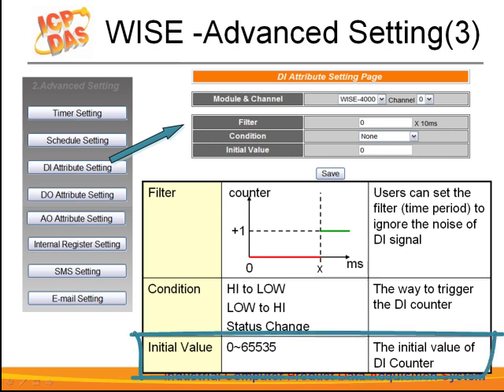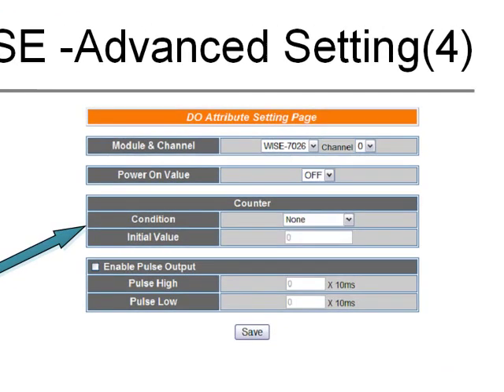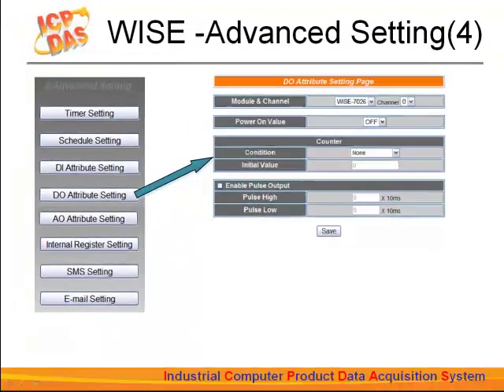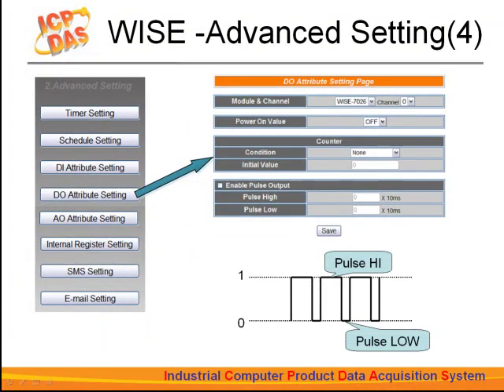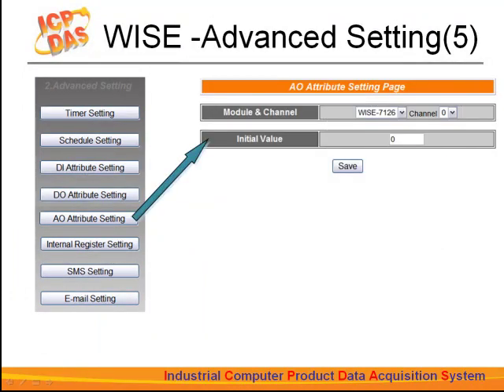You can also set the initial value of the counter in the initial value field. Now let's take a look at the digital output channel settings. You can set the power-on value to be on or off, and you can also set the counter as digital input. DO supports pulse output; you can set up pulse high and pulse low for the periodic pulse cycle. The AO attribute setting page allows you to set up an initial value for the analog output channel voltage when booting up.